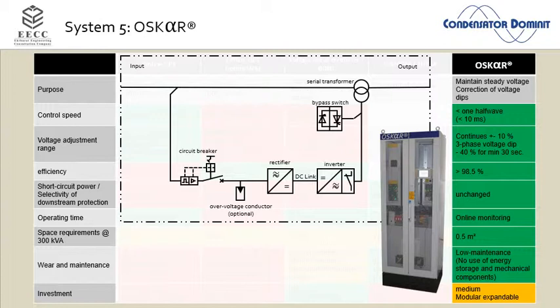And if you draw a picture for yourself, you find out that this basically means a short circuit in 3 phases. If I short circuit the three phases of this transformer, then the impedance of the transformer more or less goes down to zero. My short circuit current can go through. Now an IGBT bypass is a very expensive thing that only lasts for 2, 3, 4 milliseconds. In that time, a thyristor bypass kicks in, and at the same time, 2 independent mechanical bypasses get triggered.